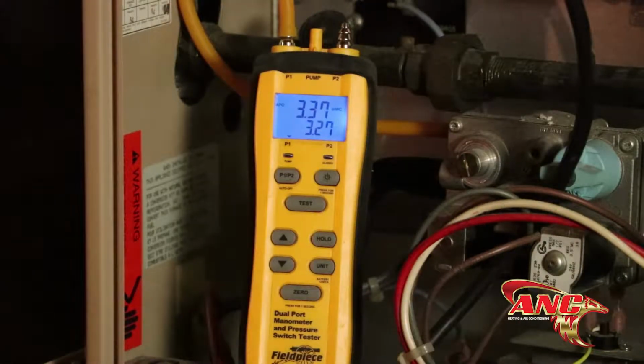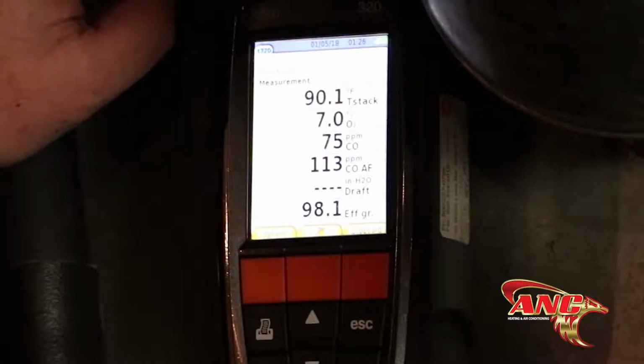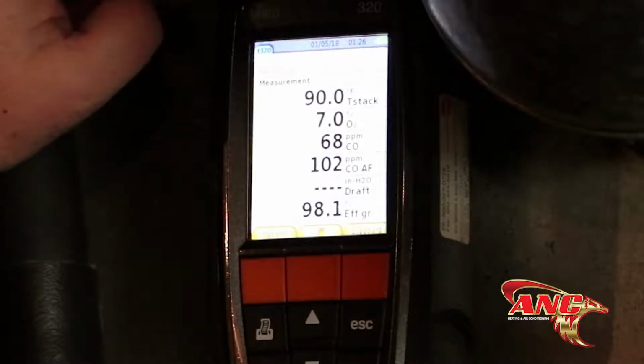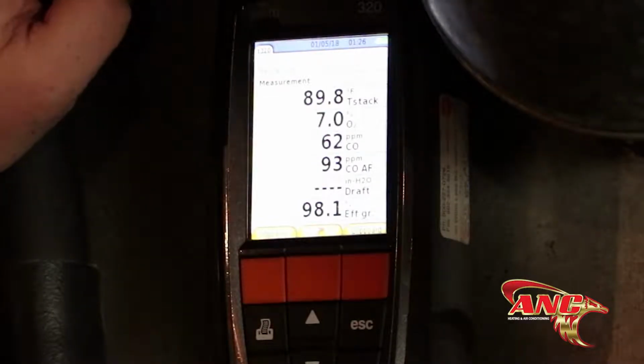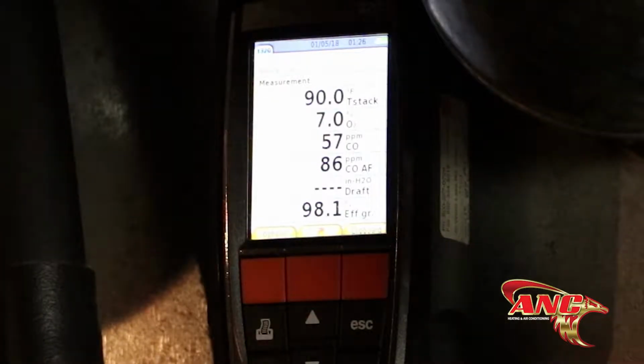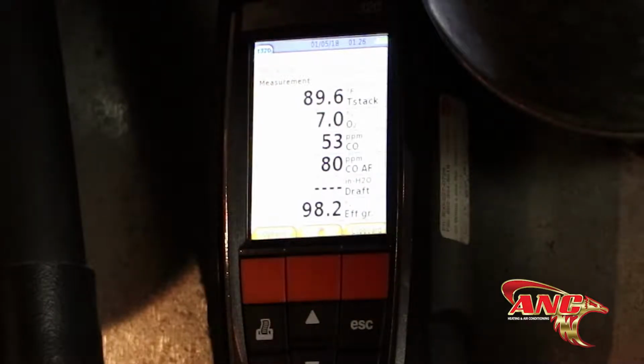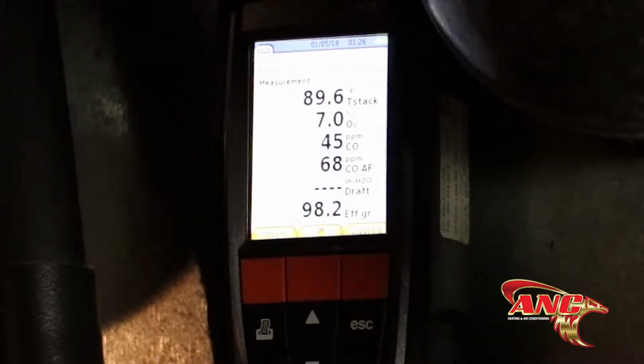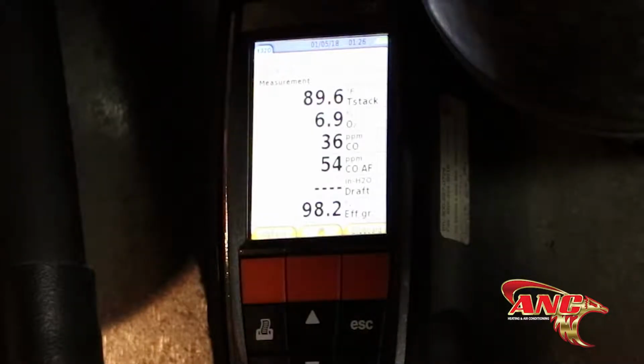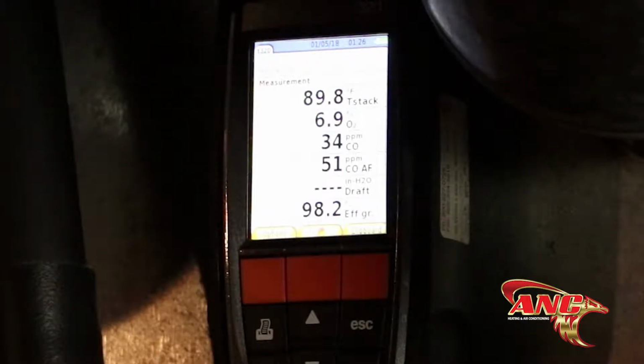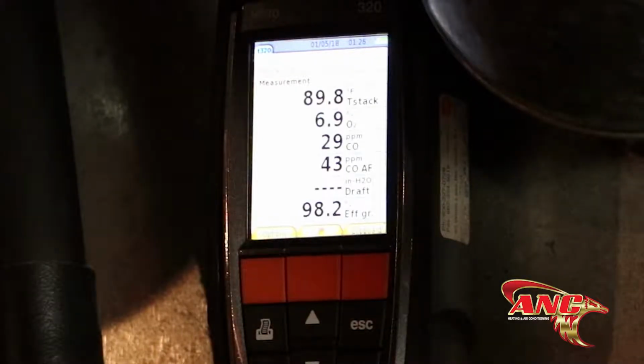We've got a gas pressure of 3.3, right on the money. We're within safe specs now, but we're going to see where it's going to land. I've had a lot of experience where after a few minutes, numbers start to creep up. You have porous holes or small cracks, and as they warm up, sometimes they actually open, which changes the readings quite a bit. But we're looking pretty good here.